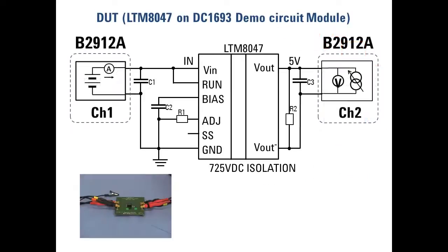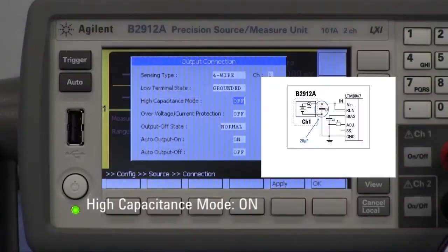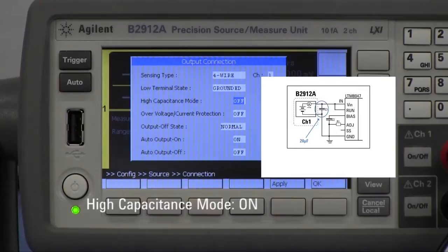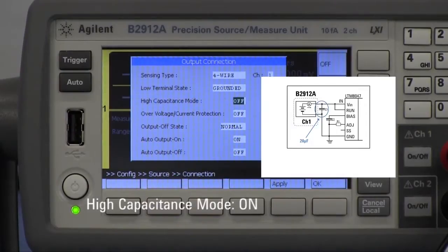The channel 1 and 2 of the B2912A are connected to the input and output terminals of the demo circuit module respectively, and 4-wire connection should be used for both channels. Since demo circuit module has load capacitance between its input terminals, high capacitance mode should be enabled on channel 1.